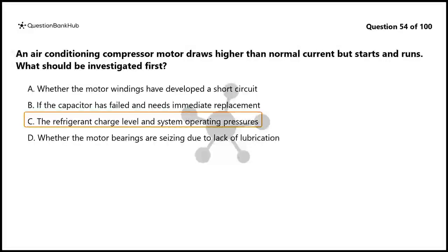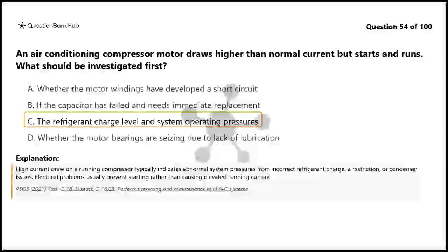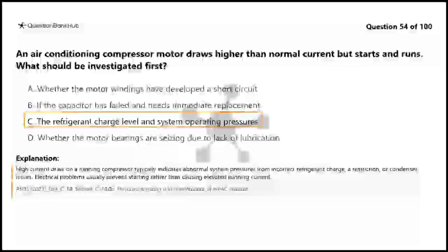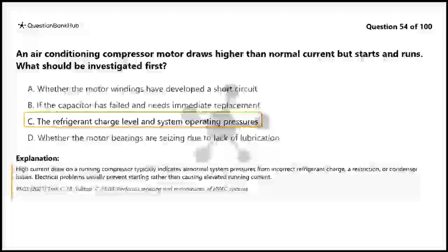The correct answer is C. The refrigerant charge level and system operating pressures. High current draw on a running compressor typically indicates abnormal system pressures from incorrect refrigerant charge, a restriction, or condenser issues. Electrical problems usually prevent starting rather than causing elevated running current.